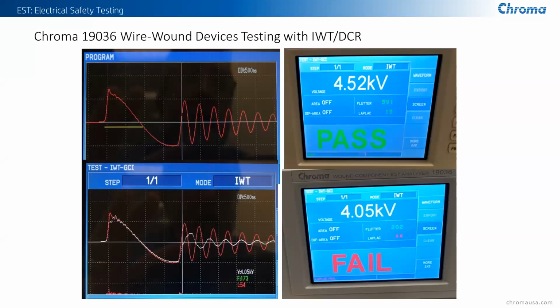A typical test would look something like this. I apologize, I took a quick snapshot of the two screens with my camera, and they didn't come out the best. But you can see a typical good waveform with the top program view. And you'll see that when we impose that pulse of short duration voltage applied from the capacitor, and as it starts to ring, it's a fairly clean waveform.